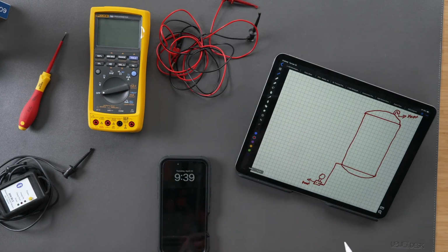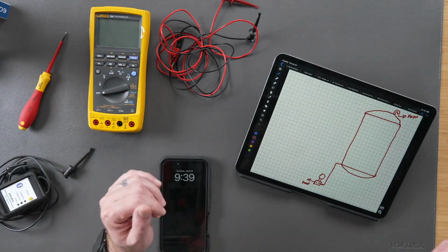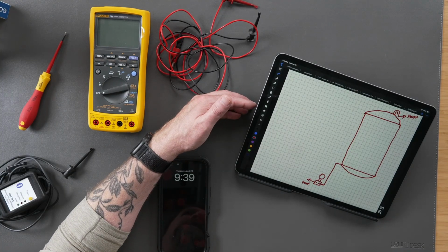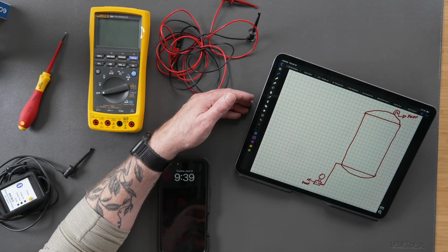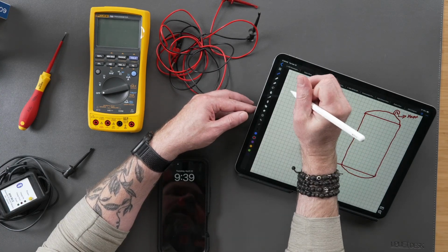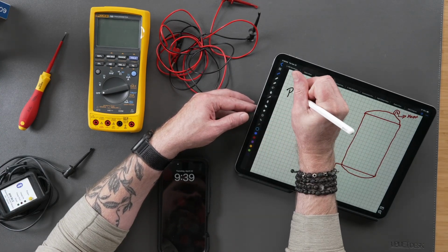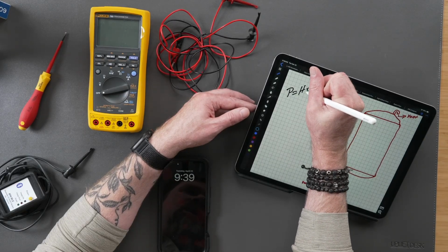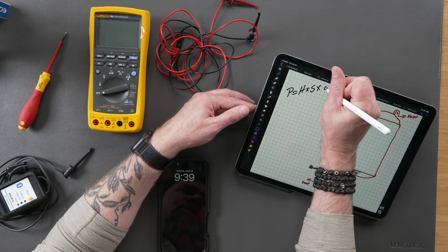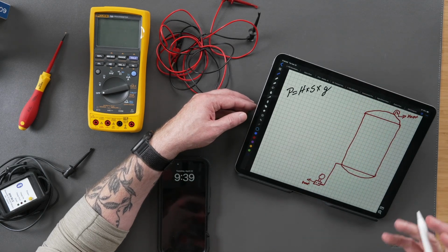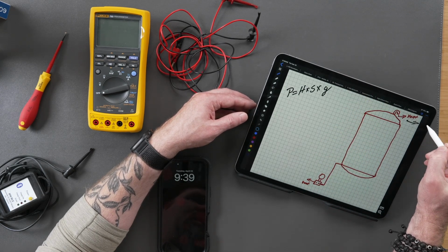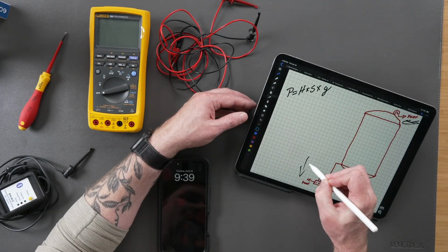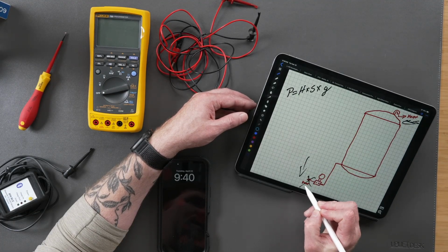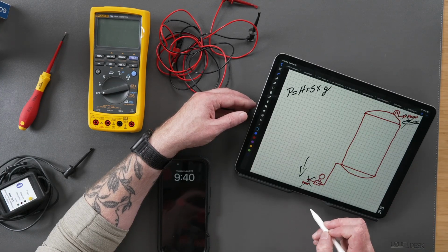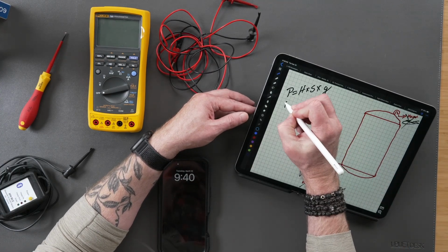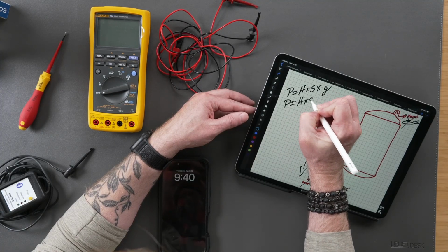Okay, so we're using a differential pressure transmitter. Typically, when you're talking about calculating pressure for a level application with a pressure transmitter or a differential, the baseline equation is pressure equals height times specific gravity times gravity. In this scenario we're getting rid of the gravity, because I've got gravity being applied here and gravity being applied here, so I can get rid of this and this. Now we're stuck with pressure equals height times specific gravity.